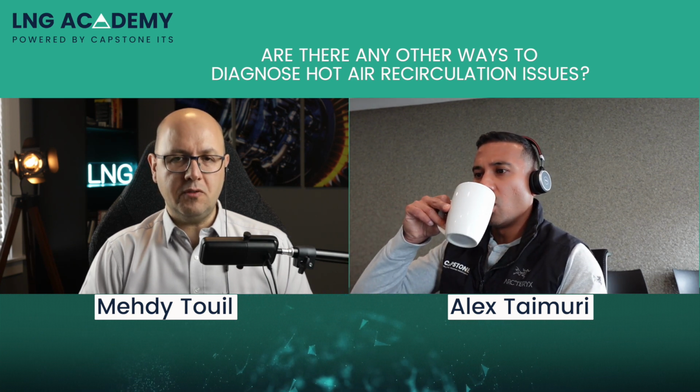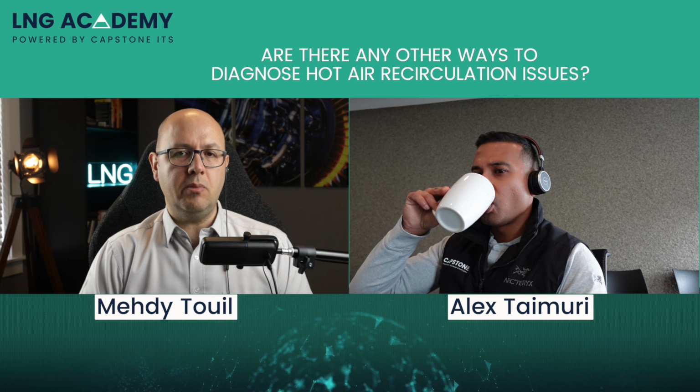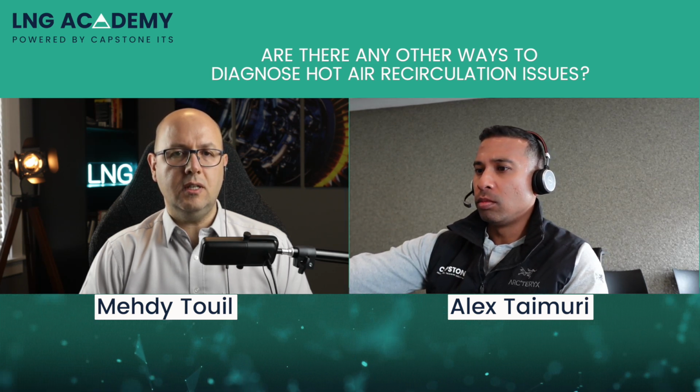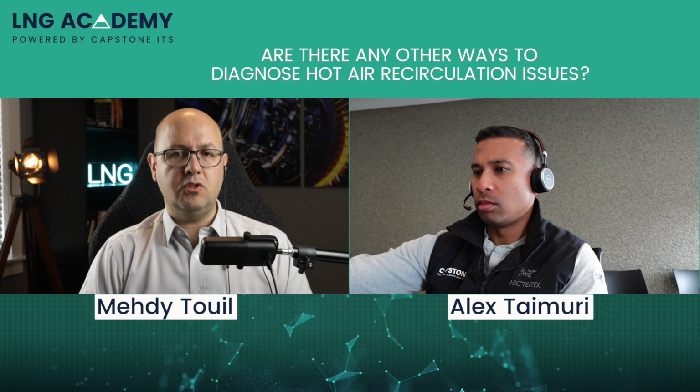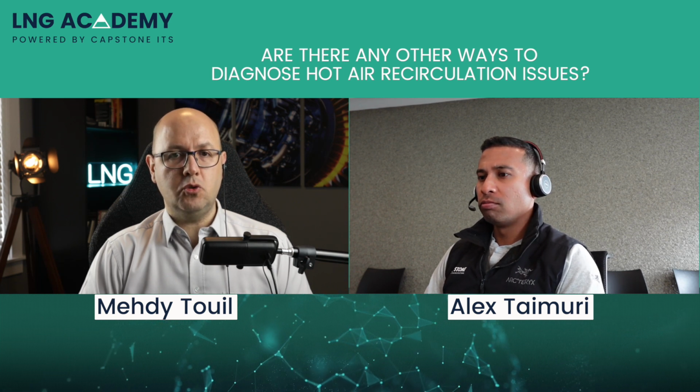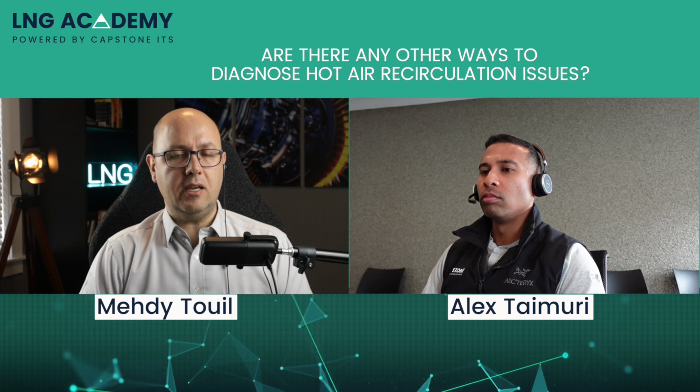Some hardware modifications can also be implemented to reduce the severity of recirculation, like the installation of chimneys or windscreens on the impacted condensers. These changes, however, should be considered with caution, as they may also reduce inlet airflow. The effect on the cooler performance could therefore be worse than the gain recovered on hot air recirculation.